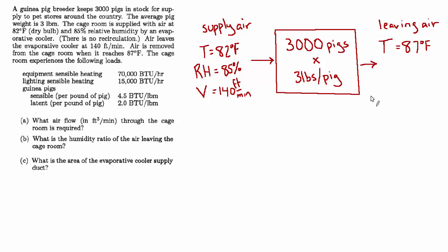So for the first question about what air flow is required, that's really going to be based on the sensible cooling requirement only. And then some amount of humidity will be added to that air while it's in the cage room. And then when it leaves, it'll be more humid. So let's summarize all the loads and get a handle on what the total sensible and total latent load are inside the cage room. And we can make a table for this.